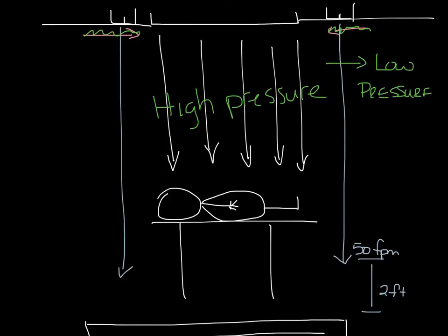You would put your returns on a low sidewall about here. So you bring air in at the ceiling level and return it out by the floor. You'll want at least two return grills located about three foot above the floor.